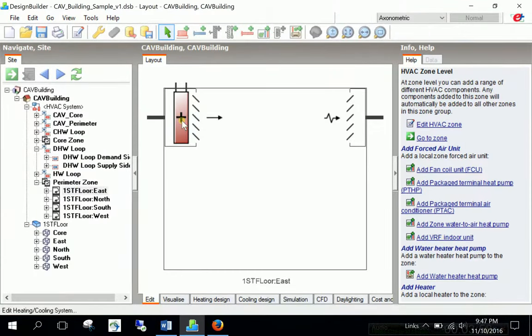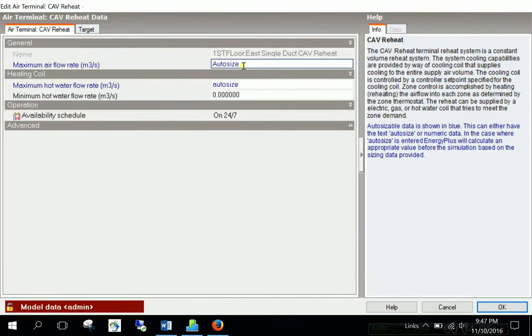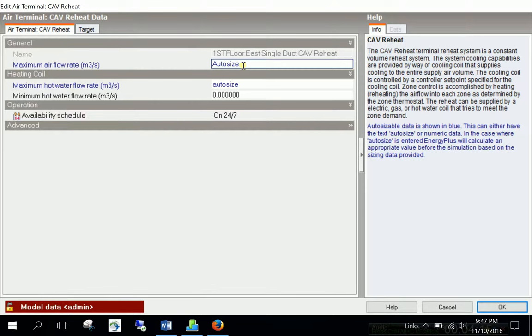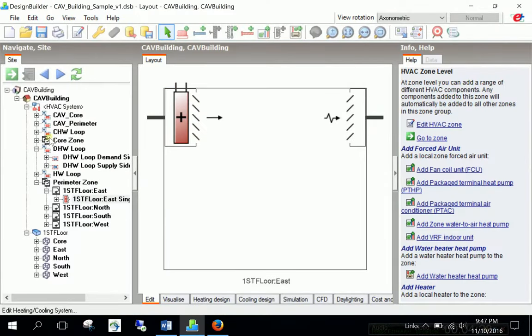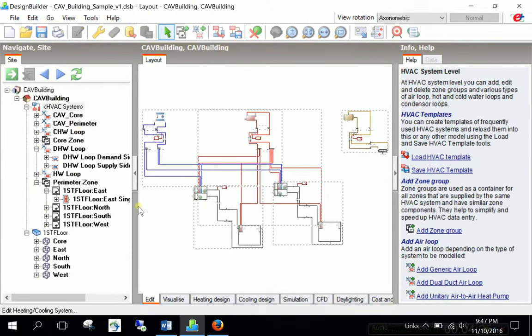Look here. It was different from VAV system. This time we don't have dampers. We have less number of settings. We don't have maximum reheat temperature. Remember in the VAV there was this maximum reheat temperature and the default was 35 degrees C. This time we don't have it because it's missing from the settings because we don't have the variable air volume system. Totally different but nothing to do basically because things are autosized. So say okay and go back to HVAC system.